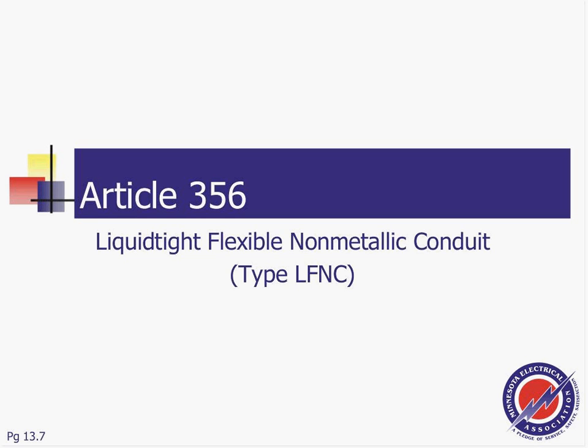Any questions about that? Any questions before we move into liquidtight flexible nonmetallic conduit? So what we did, guys, we went over flexible metallic conduit and Liquidtight flexible metallic conduit, and we see the only major difference between them is really wet locations. That's the major difference between them. Other than that, they are identical, and it's cheaper to use the flexible conduit.